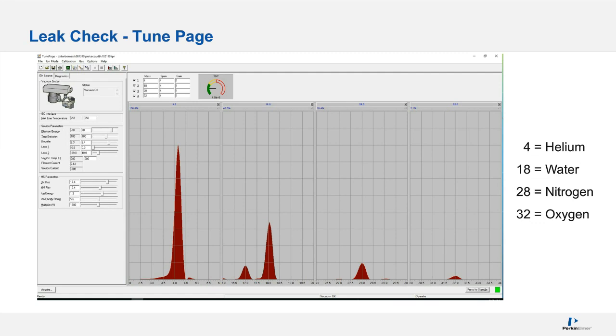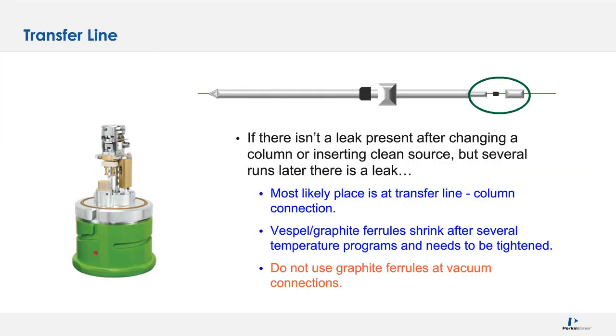So the first time I see a leak, the first place I check is at the connection of the mass spec transfer line. That's because of that Vespel graphite ferrule. My service engineers keep their ferrules in the GC oven just so they're always set. But when you put on a fresh ferrule and it goes through a temperature ramp, it contracts and we need to reset it. So what I usually do is bring up my oven temperature, bring it down, and reset the ferrule. I do that twice.